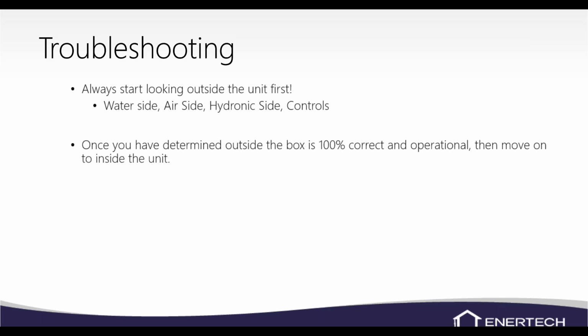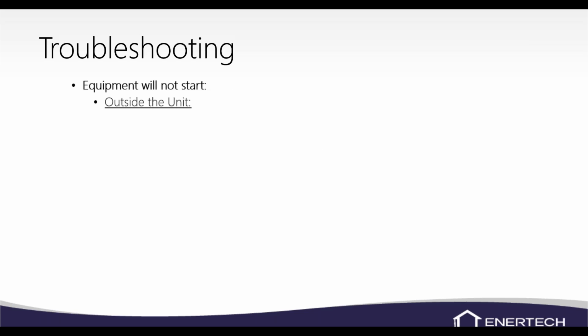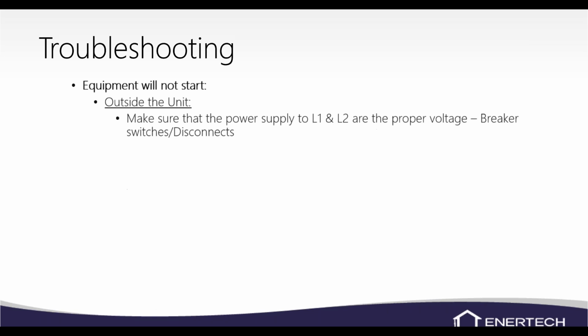Once you have determined outside the box is correct and operational, then we'll go ahead and move to the inside of the unit. So if the equipment will not start, so it's, you know, the compressor is not running, the fan's not running, outside the unit, what would we want to check? Obviously, we want to make sure we've got power at L1 and L2. We got proper voltage there. You know, if you don't have proper voltage coming into the unit, then obviously we need to check our breakers. If you've got a disconnect, we need to make sure that disconnect is okay, that the blades are in the proper position. And if it's got fuses in that disconnect, make sure those fuses are good as well.